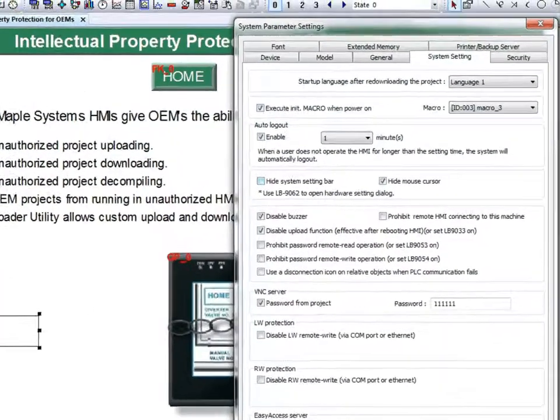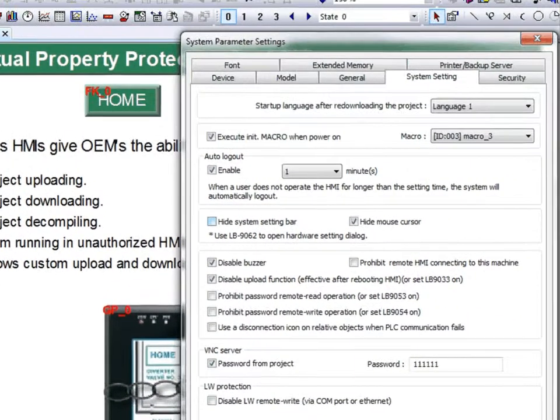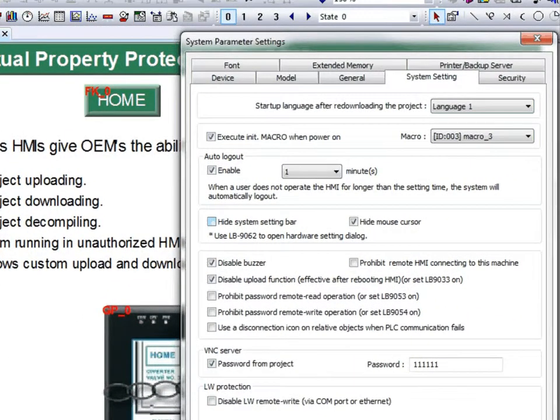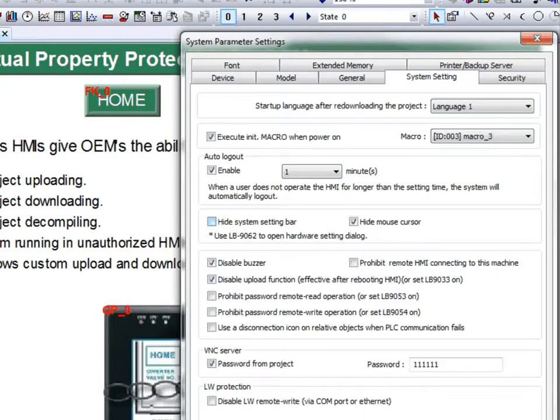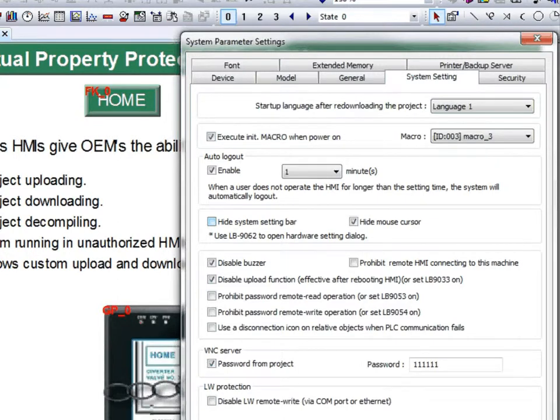The hide system setting bar option will hide the system setting button on the HMI, keeping the user out of the HMI's settings menu. Once this checkbox is checked and the project is downloaded to the HMI, the only way to turn the system setting button back on is to uncheck this box and re-download the project.